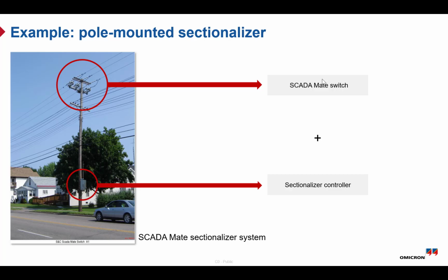The sectionalizer operates together with an upstream device like a recloser. When the fault happens, the recloser clears the fault current first. During the open or dead time of the last reclose shot, the sectionalizer opens to isolate the faulted section of the line. This allows the healthy parts of the network to remain energized, which improves selectivity and overall reliability.